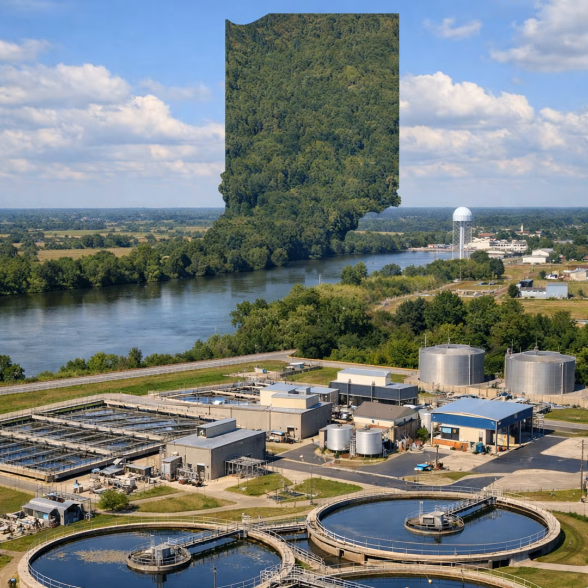Sludge volume index. That is a calculation that indicates the tendency of activated sludge solids or aerated solids to thicken or become concentrated during the sedimentation thickening process. The SVI is calculated in the following manner. To calculate an SVI, you allow a mixed liquor sample from the aeration basin to settle for 30 minutes.